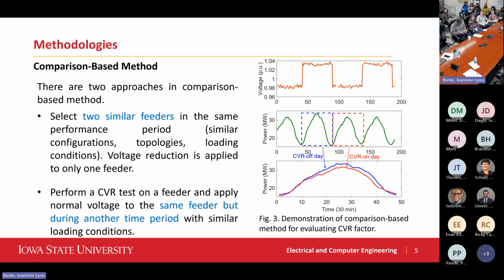Well, actually there are many simple methods used by industry. The first method we call the comparison method. Look at this figure: if you have one feeder, you do the voltage reduction, then you raise the voltage back to normal. You do this on and off, on and off, and measure the power. So one thing you might claim is that the difference between these two power curves is the reduction due to your voltage reduction.